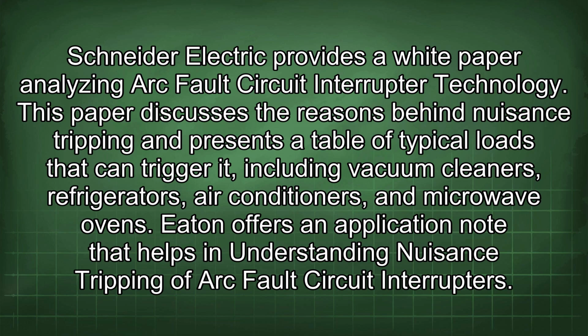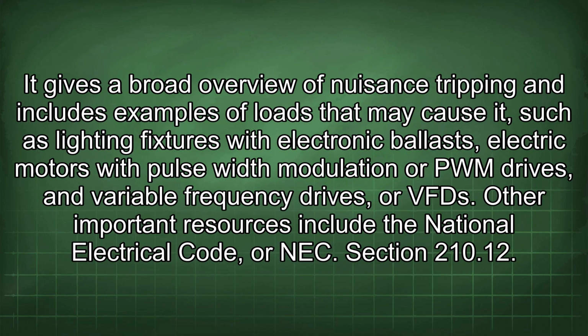Eaton offers an application note that helps in understanding nuisance tripping of arc fault circuit interrupters. It gives a broad overview of nuisance tripping and includes examples of loads that may cause it, such as lighting fixtures with electronic ballasts, electric motors with pulse width modulation or PWM drives, and variable frequency drives, or VFDs.